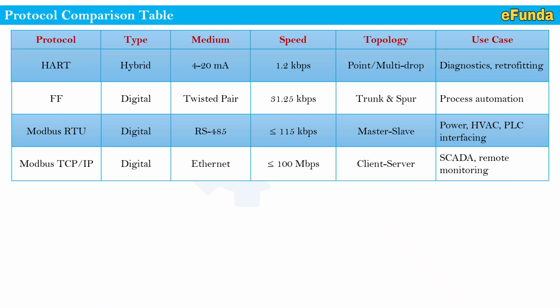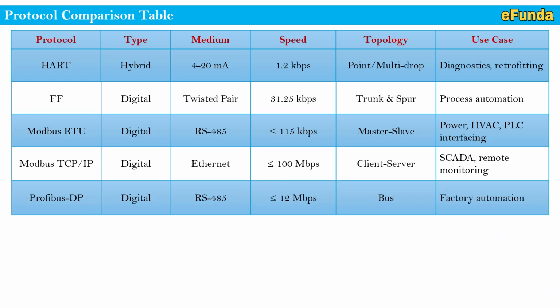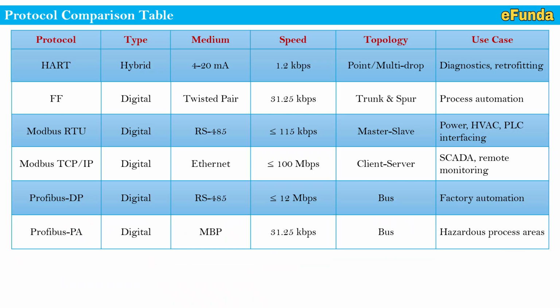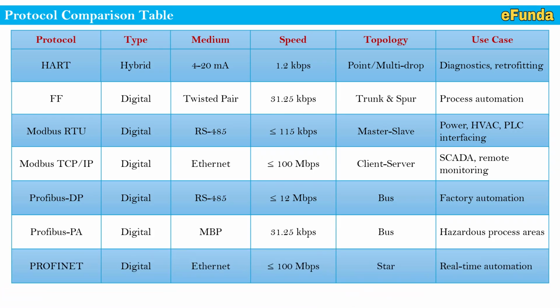Modbus TCP/IP is a digital type, Ethernet medium, speed less than or equal to 100 Mbps, topology client server, used for SCADA remote monitoring. Profibus DP is a digital type, medium RS485, less than or equal to 12 Mbps, bus type topology, used for factory automation. Profibus PA is a digital type, medium MBP, speed 31.25 kilobits per second, bus type topology, used in hazardous process areas. Profinet is a digital type, medium Ethernet, less than or equal to 100 Mbps, star type topology, used for real-time automation.